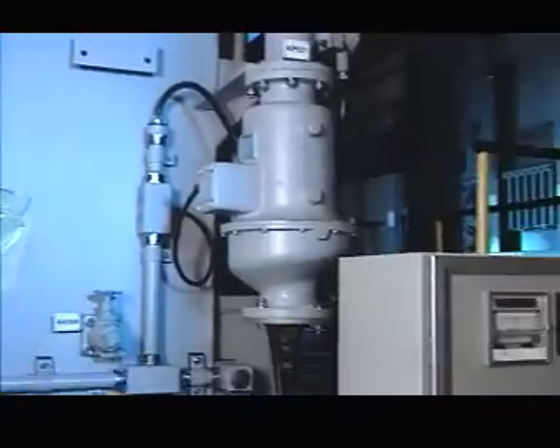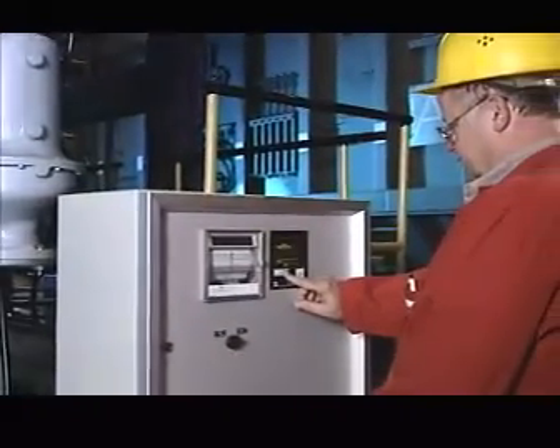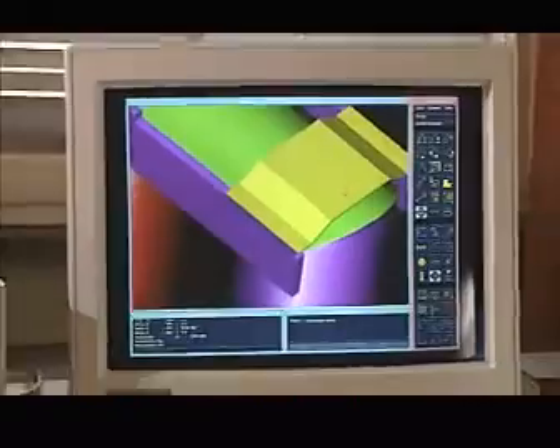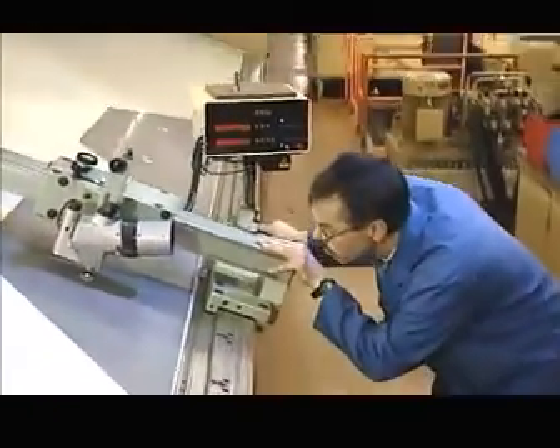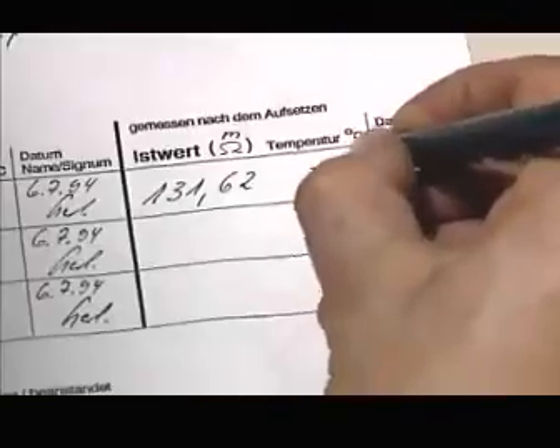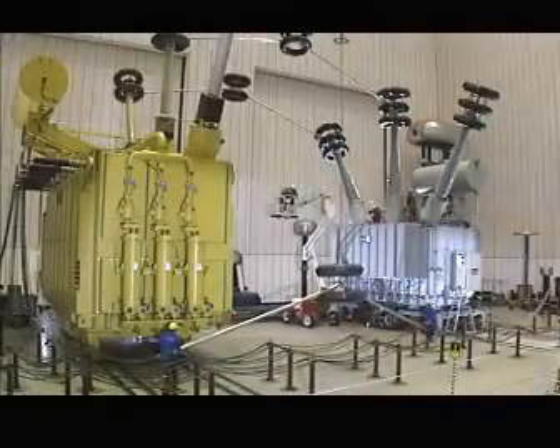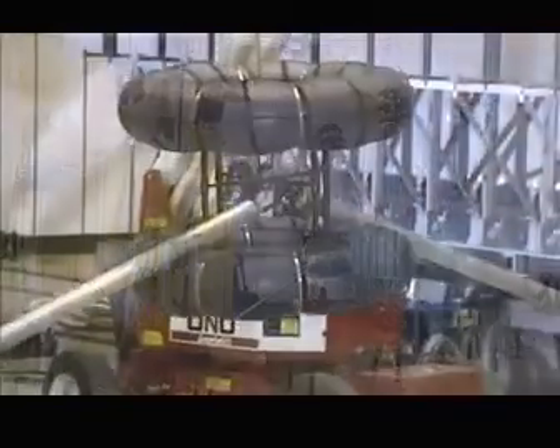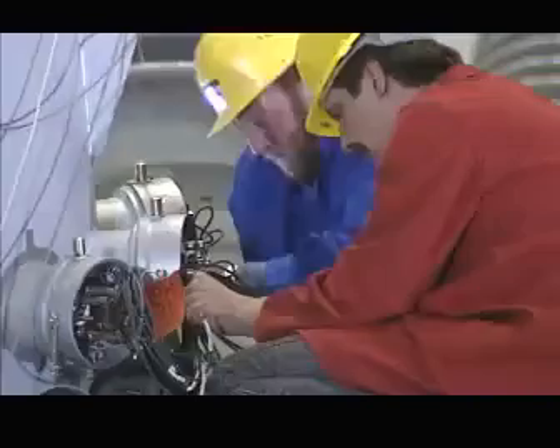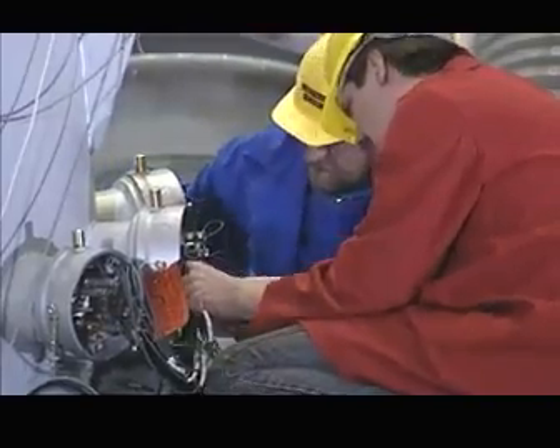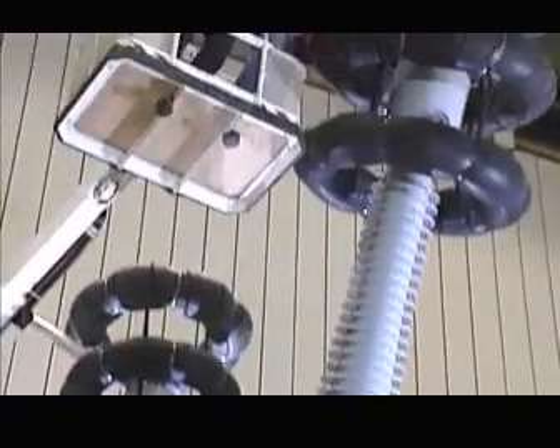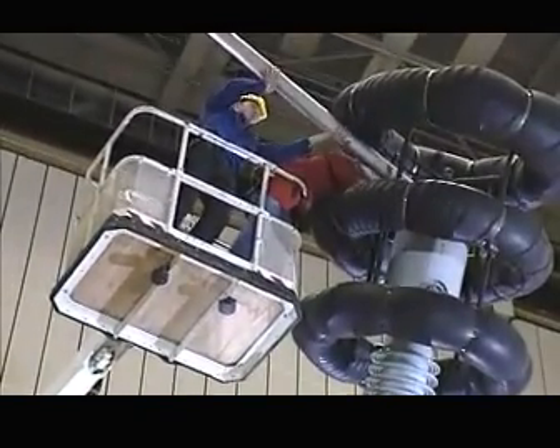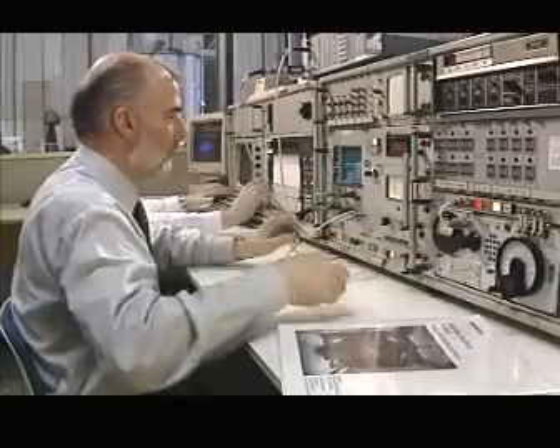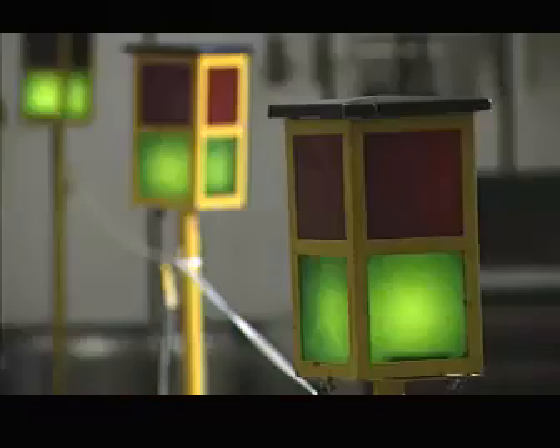After final assembly, the tank is evacuated, filled with mineral oil and tested. Our quality management system accompanies all the production steps, from design and development via production right through to the final checks. Before the transformer is handed over to the customer comes the toughest test, the electrical and mechanical quality check in our accredited test fields. Here we test transformers and shunt reactors with rated powers of up to 1500 megavolt ampere and line voltages of 1500 kilovolt.